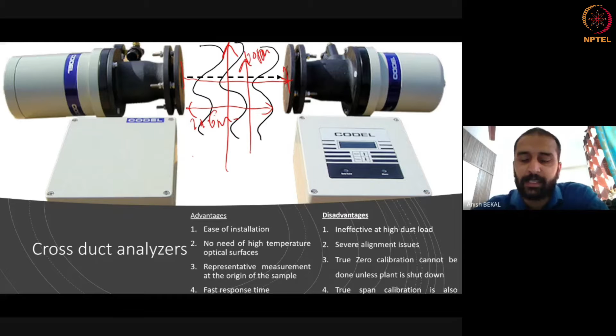This is another type of analyzer where you have an in situ probe. So your stack basically comes in this region, and the analyzer is basically inserted into the stack, and you have the light bouncing off a mirror that is placed here. And if you see here, this is a long probe that is inserted into the stack, right? So this long probe has several filters on it. And these filters are very, very minute filters, which have a filtration capacity of 20 microns, or in many cases 2 microns. And they won't allow the dust to come in. Only the gas would diffuse through these filters into the chamber where the measurement is done, and the light is basically passed through the gas to make your measurements. By doing this again, you can measure many of these concentrations.